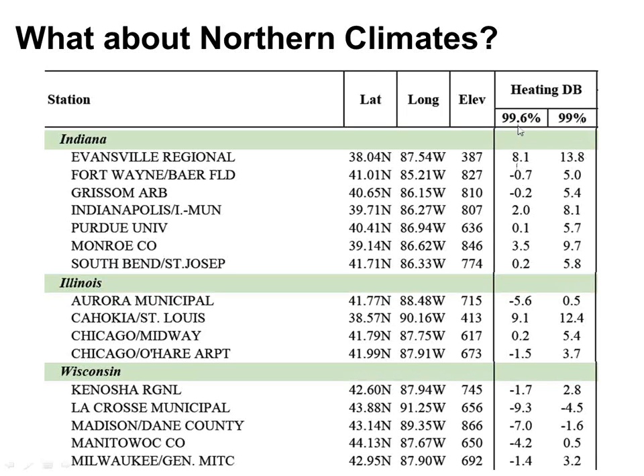For the other column, 99.6% of the time, it's going to be above that number. Basically meaning there's a 0.4% chance that you might have an hour of the day that you drop below these temperatures. Generally, that happens at night when you don't care about heat as much anyway. Commercially, your building might be shut down. Residentially, hopefully you're under the covers, so it's not as big of a deal.